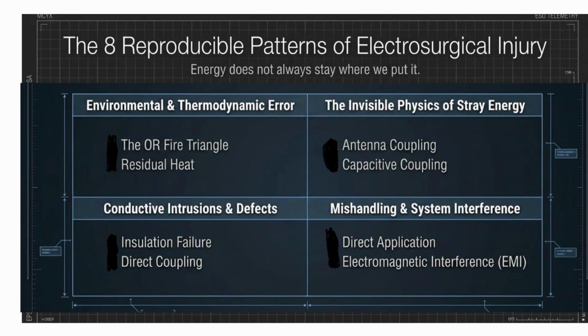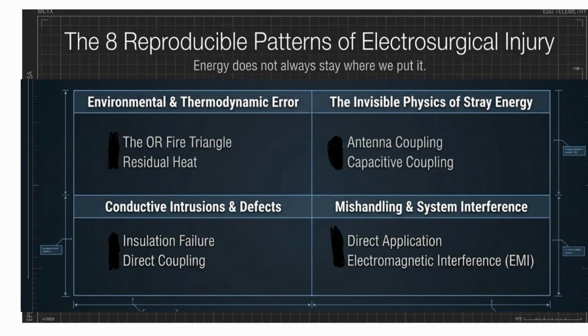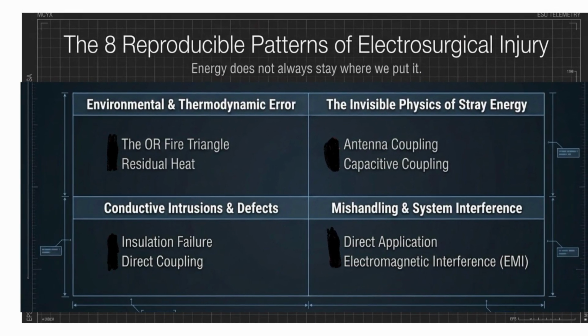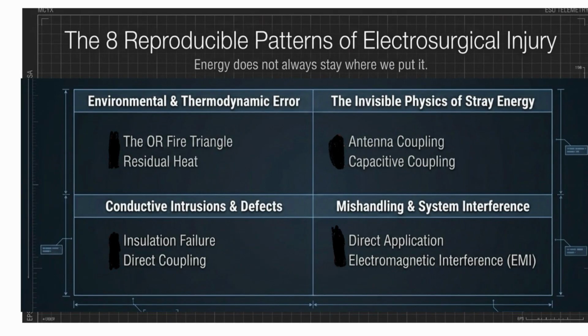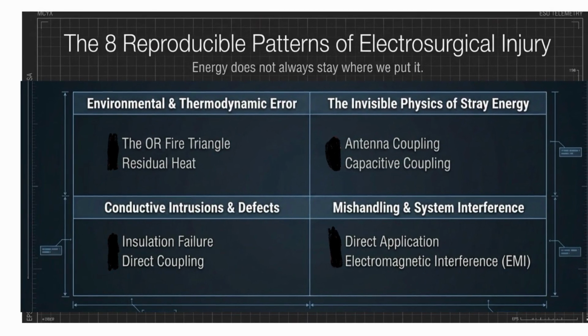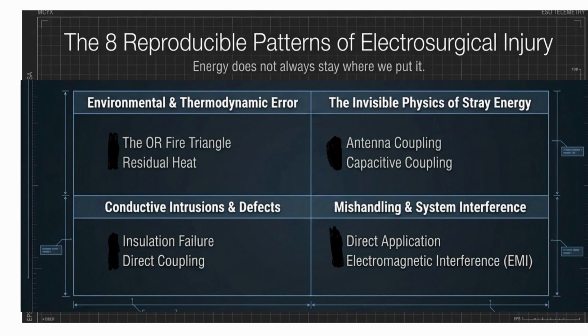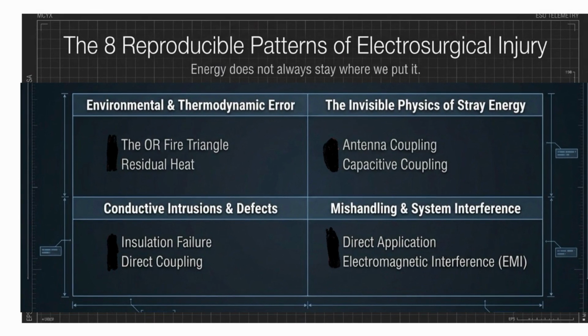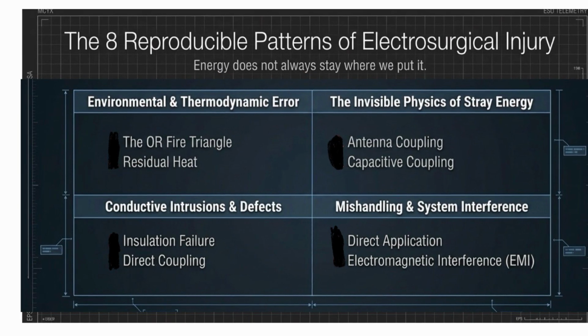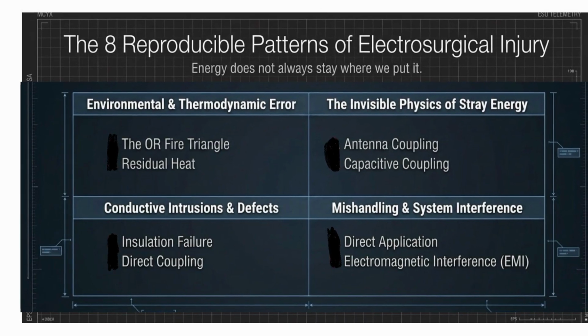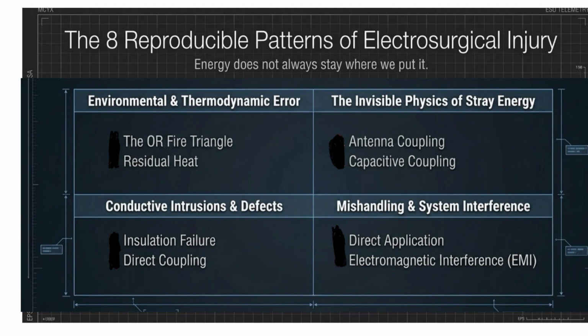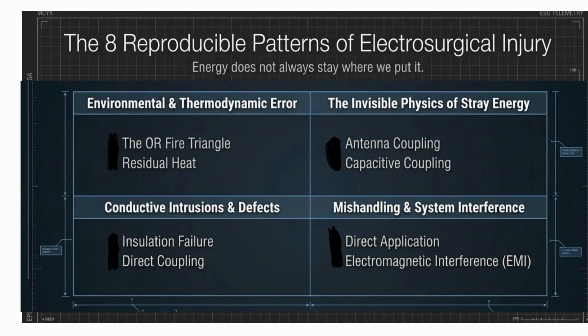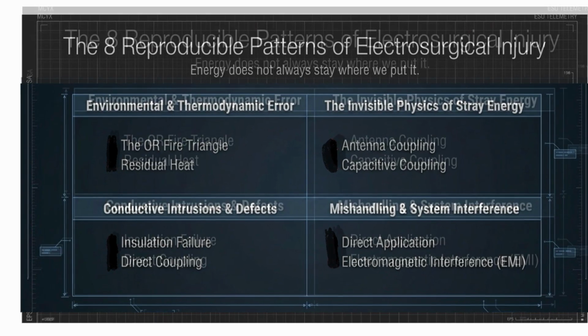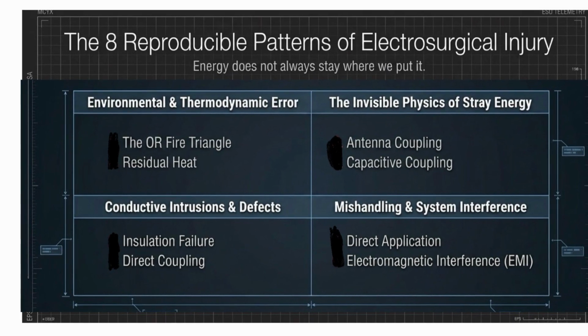The hazards or electrosurgical injuries: environmental and thermodynamic errors are the OR fire triangle and the residual heat; the invisible physics of stray energy, the antenna coupling and the capacitive coupling; conductive intrusions and defects, insulation failure and direct coupling; mishandling and system interference, direct application, electromagnetic interference.